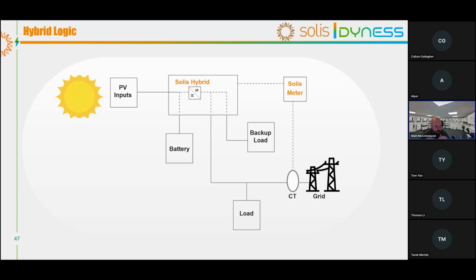You can see sort of overspill. So what you might see is that you might be pulling 40 watts from the grid for a short period of time, or you might be exporting 40 watts to the grid, but it's basically just a balancing act. So it's dynamically figuring out what the load is doing, what the grid is doing, and what the hybrid inverter is doing, and then sending signals to the inverter in order to react to that.